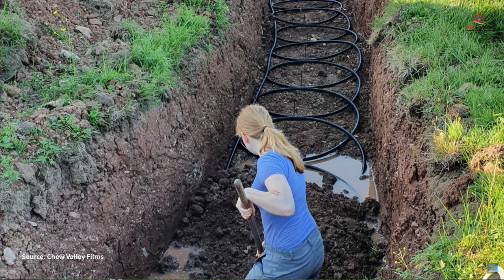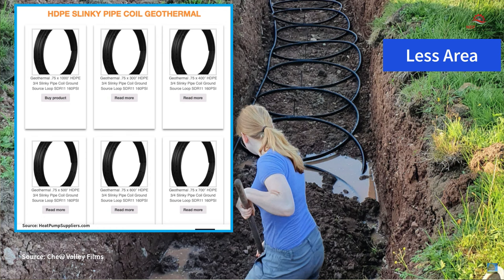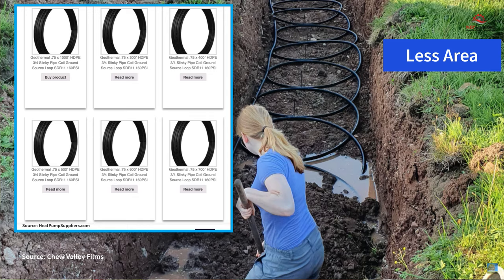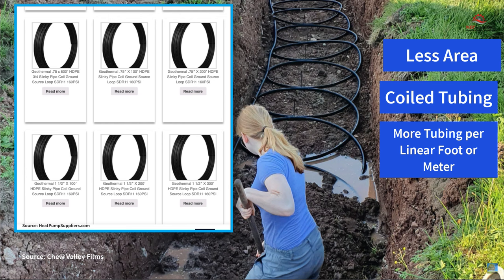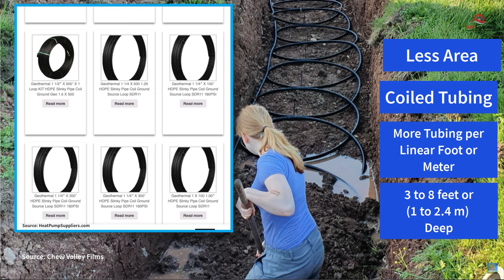The Slinky Geothermal Loop Installation: This geothermal system uses coiled tubing which allows for the use of less area by increasing the heat transferability per area used. The tubing is coiled in the trench, requiring less land area but more tubing per linear foot. The coils are laid in a horizontal trench 3 to 8 feet (1 to 2.4 meters) deep. A combination of water and antifreeze circulates through the tubing and the heat pump's heat exchanger.